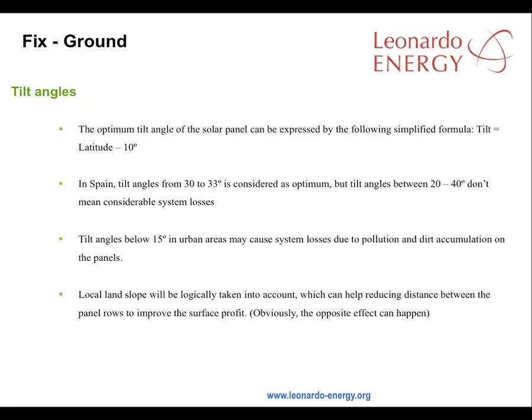The optimum tilt angle of a solar panel can be expressed in a simple formula: tilt is equal to latitude minus 10 degrees. In Spain, tilt angles from 30 to 33 degrees are considered the optimum. But tilt angles anywhere between 20 and 40 degrees will not result in considerable system losses. Tilt angles below 15 degrees in urban areas may cause system losses because of pollution and dirt accumulation on the panels.